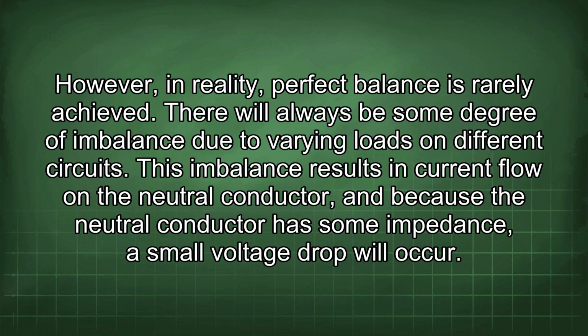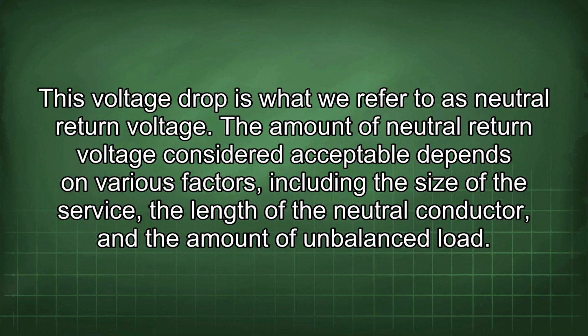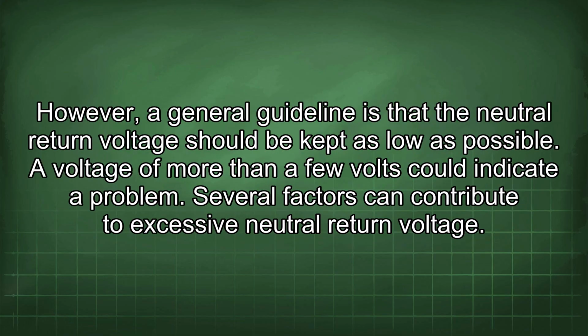However, in reality, perfect balance is rarely achieved. There will always be some degree of imbalance due to varying loads on different circuits. This imbalance results in current flow on the neutral conductor, and because the neutral conductor has some impedance, a small voltage drop will occur. This voltage drop is what we refer to as neutral return voltage. The amount of neutral return voltage considered acceptable depends on various factors, including the size of the service, the length of the neutral conductor, and the amount of unbalanced load. However, a general guideline is that the neutral return voltage should be kept as low as possible. A voltage of more than a few volts could indicate a problem.